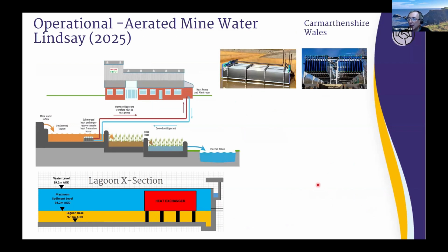Turning now to the Lindsay mine water treatment scheme in South Wales, we're really pleased to have completed installing an energy blade system in partnership with Thermal Earth. Turning to the graphic here, you'll see that mine water is pumped from surface and flows into a settlement lagoon where ochre precipitates. The mine water continues through reed beds where it's cleaned and filtered before discharge to the local watercourse. And Thermal Earth has installed energy blades in our lagoon, and that's taking waste mine water heat to their premises and plant room.